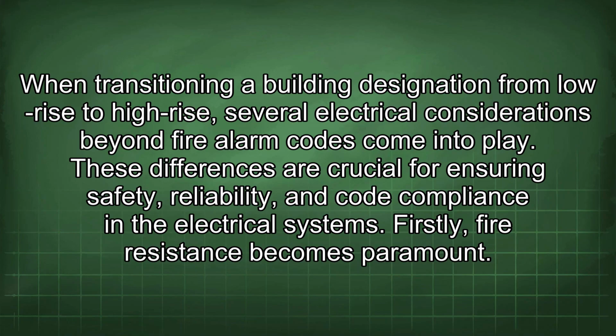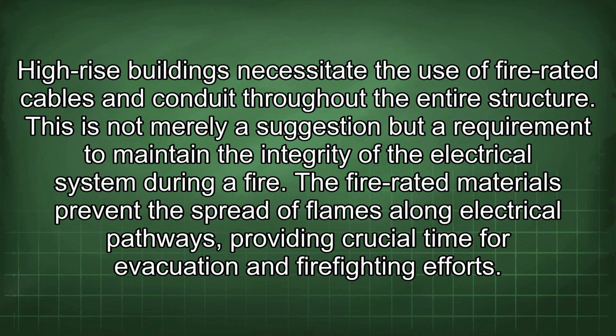When transitioning a building designation from low-rise to high-rise, several electrical considerations beyond fire alarm codes come into play. These differences are crucial for ensuring safety, reliability, and code compliance in the electrical systems. Firstly, fire resistance becomes paramount. High-rise buildings necessitate the use of fire-rated cables and conduit throughout the entire structure. This is not merely a suggestion, but a requirement to maintain the integrity of the electrical system during a fire. The fire-rated materials prevent the spread of flames along electrical pathways, providing crucial time for evacuation and firefighting efforts.